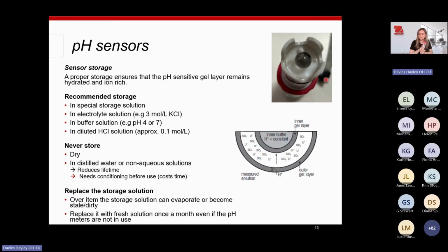How do we store them? Whenever you buy an electrode, it should be supplied with what we call a wetting cap. Our wetting caps have a little tiny sponge in the end. These are designed to be cleaned and then replaced with the recommended storage solution or electrolyte solution. You can pop a few drops in there and pop the lid on, and that will make sure it keeps the electrode's glass membrane nice and hydrated and ion rich. Never, ever, ever store it dry, because you will affect this gel layer.